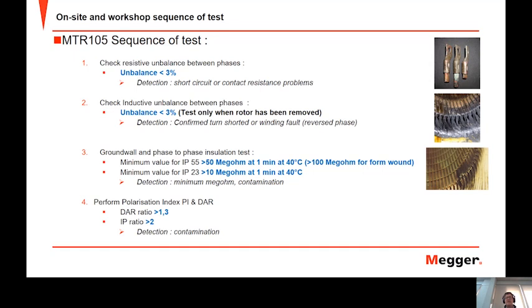And then finally, we have the PI test or the DAR test. The PI test is typically performed on high voltage machines only, and we're looking for that contamination mainly, but also brittle or damaged insulation in the slot portion.